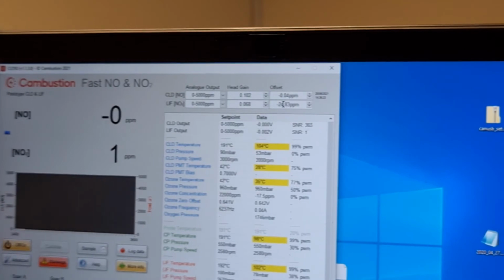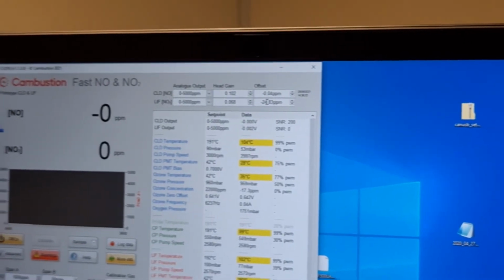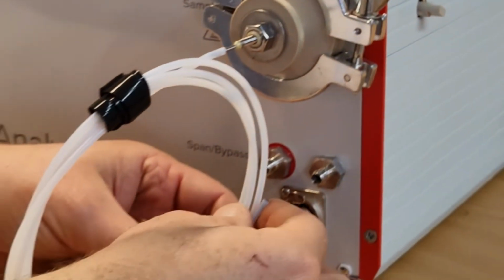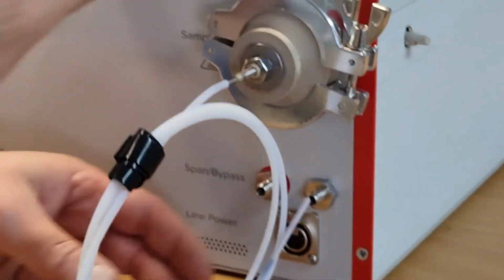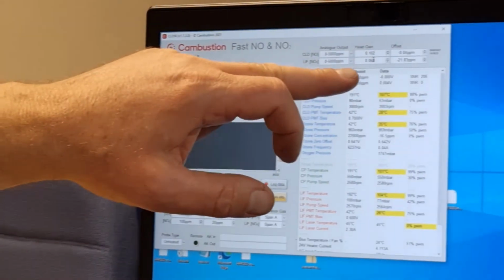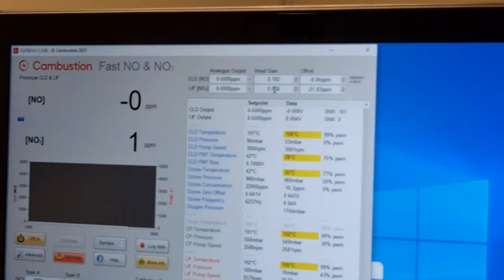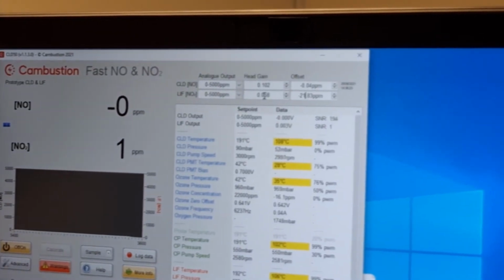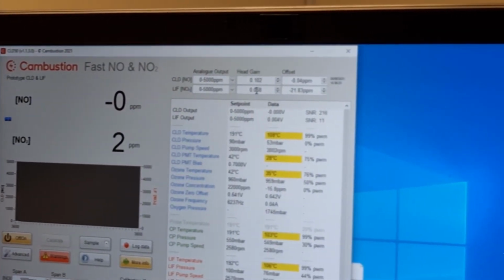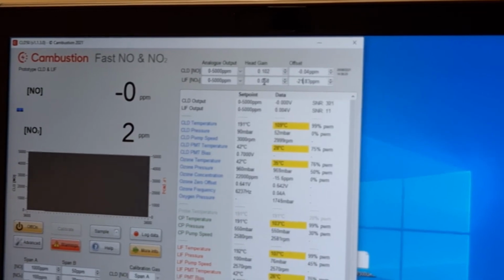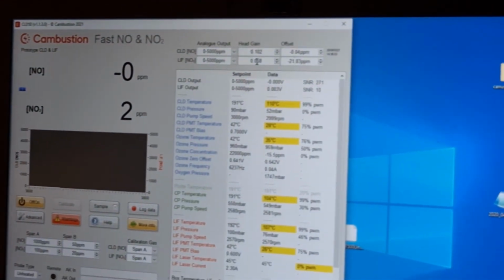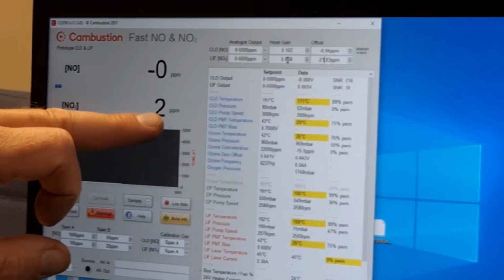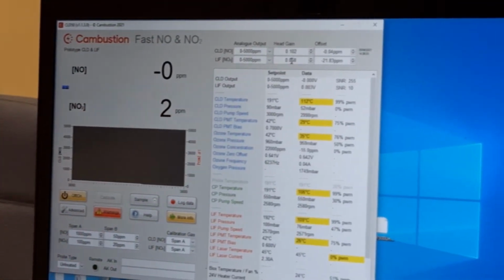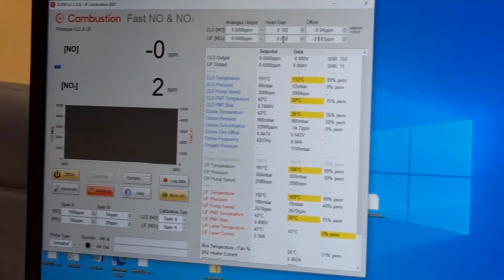If I manually calibrated the system by putting calibration gas from a bottle over the tip of this unheated sample probe, I could change the output level by altering the head gain. So a larger number there will amplify the raw signal to a greater degree. And so if I put in 10 ppm span gas, I would basically adjust that head gain to give me 10 ppm output here, and giving it 0 gas, I would adjust this to 0.